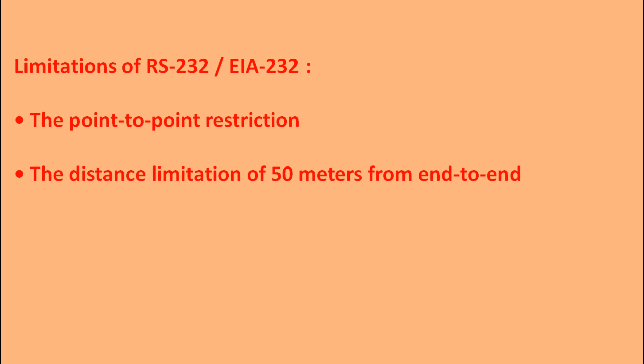The main limitations of EIA-232 when used for instrumentation and control equipment in an industrial environment are: point-to-point restriction — it enables communication across only two points, which is a severe limitation when several smart instruments are used; distance limitation of 50 meters end to end, which is too short for most control systems; and a maximum speed of 20 kbps, which is too slow for many modern applications.